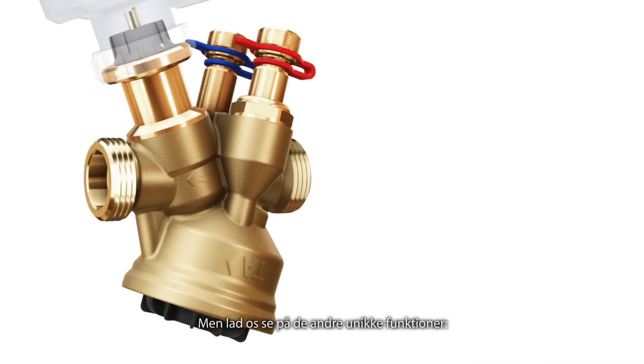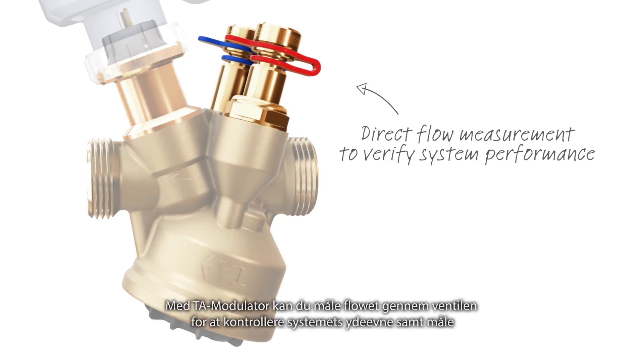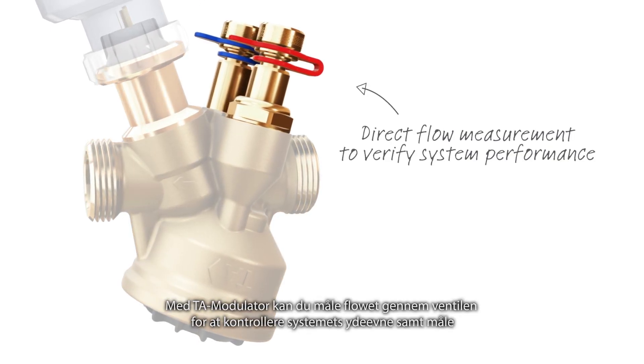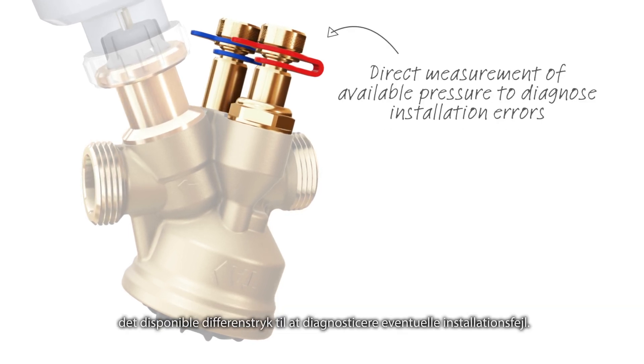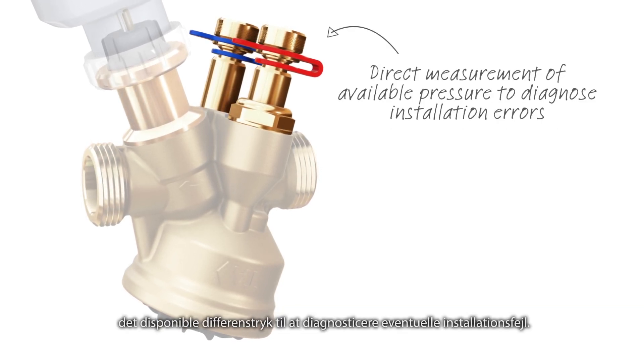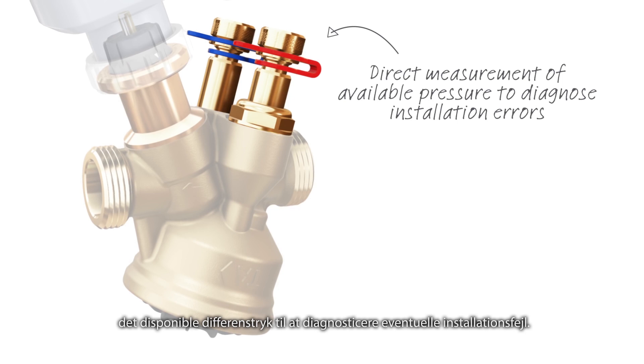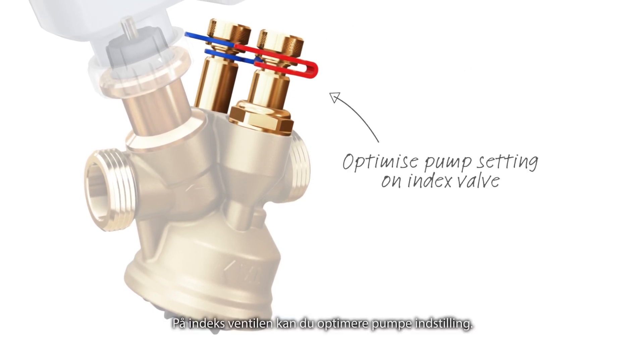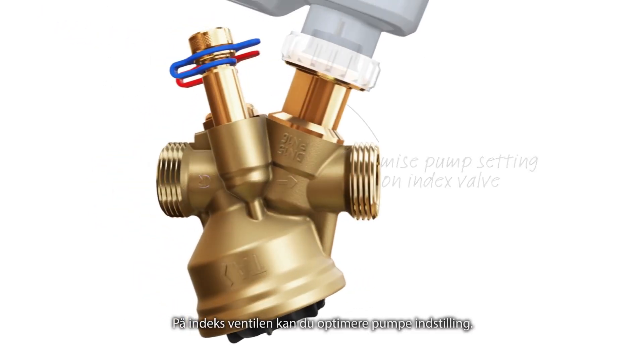But let's look at the other unique features. With TA modulator you can measure the true flow through the valve to verify the system performance, as well as measure the available differential pressure to diagnose possible installation errors. On the index valve you can optimize pump setting.